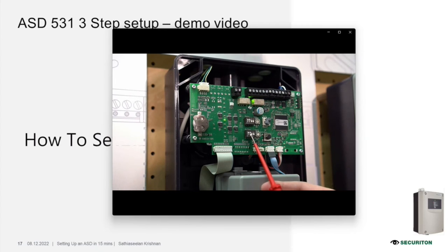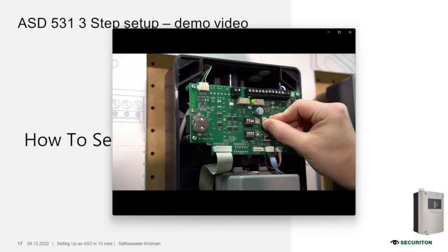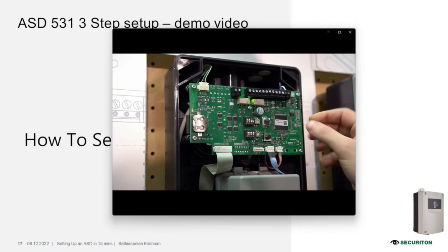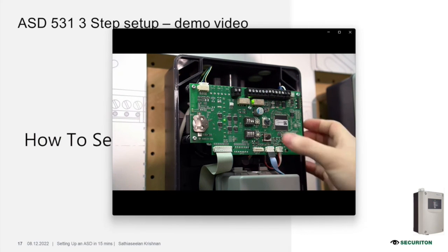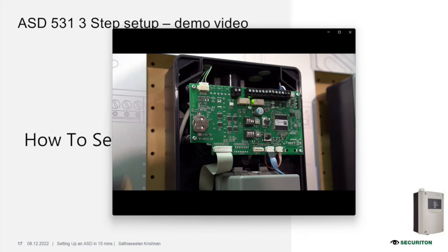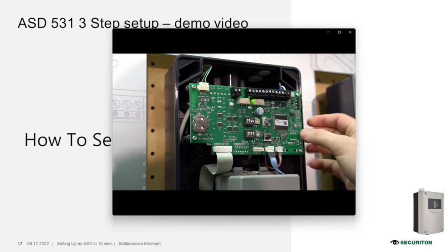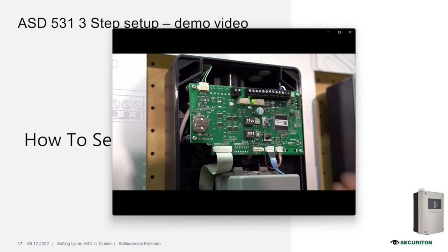Now what you're doing is additional things, which is the airflow settings that you need to do to make sure that you're within the 20%, 30%, 50%, or 10% of airflow. Then you set back into a running mode according to the system, and you reset the system, and the airflow works. And now the last point is how to remove the SD card, and you come back to normal mode again and set it up again.